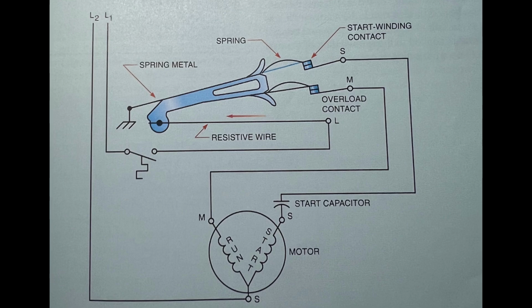In the next image, it is assumed that a thermostat controls the operation of the motor. When the thermostat closes, current flows through a resistor wire and two normally closed contacts connected to the start and run windings of the motor. The starting current of the motor is high, which rapidly heats the resistance wire, causing it to expand.